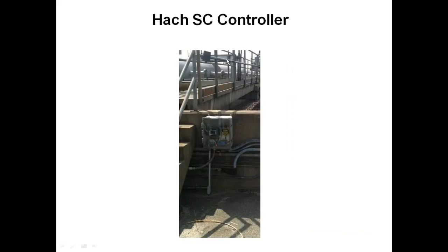Another field retrofit for people doing water and wastewater. This was a Hach SC Controller at a digester in a plant, looking at dissolved oxygen and other measurements. Once this was mounted, the customer wanted to pick one analog signal off here and run it to a maintenance building about a quarter-mile away. So this was a simple application: add a node, run the analog input into the node, map it to the gateway, and now it shows up a quarter-mile away in the maintenance shed.